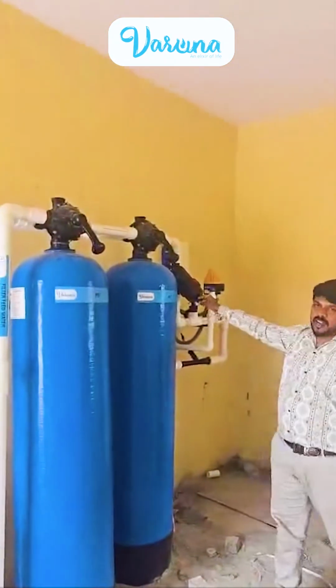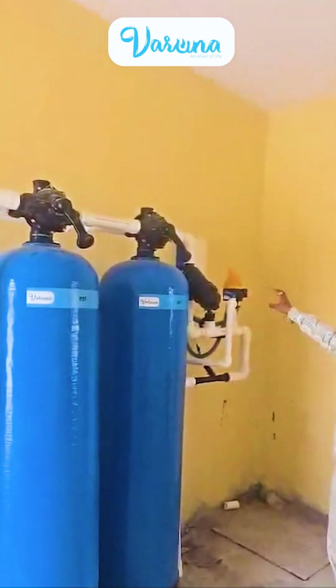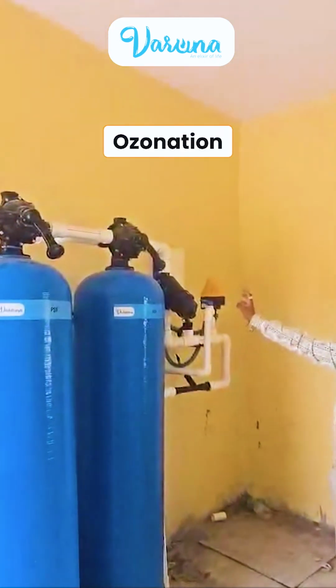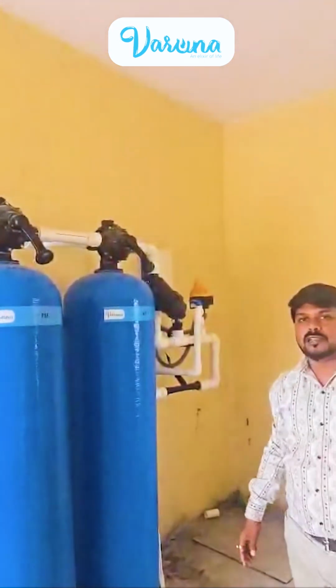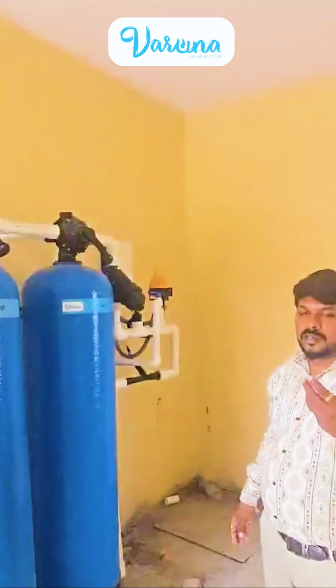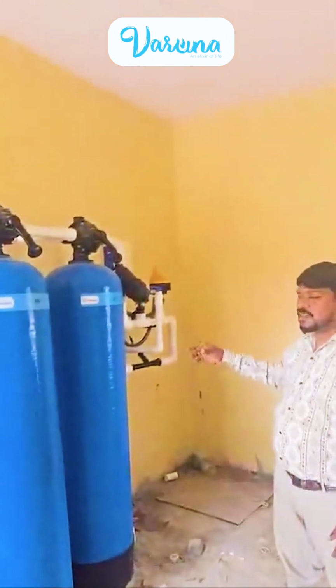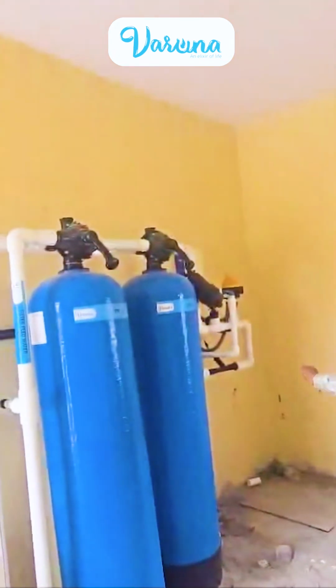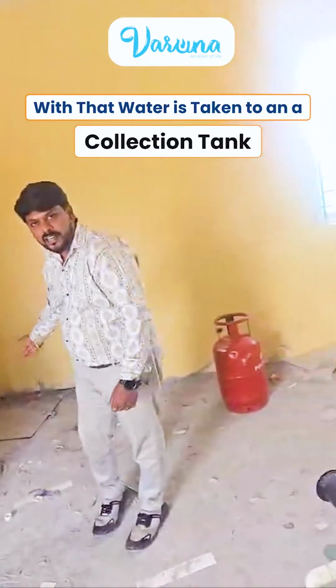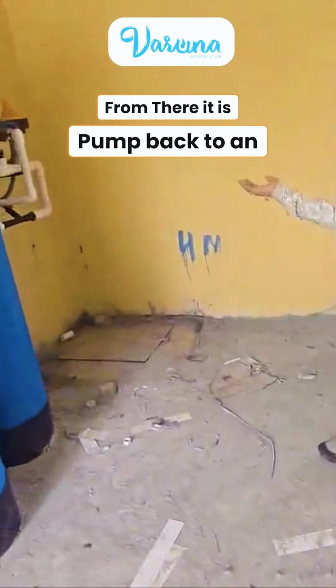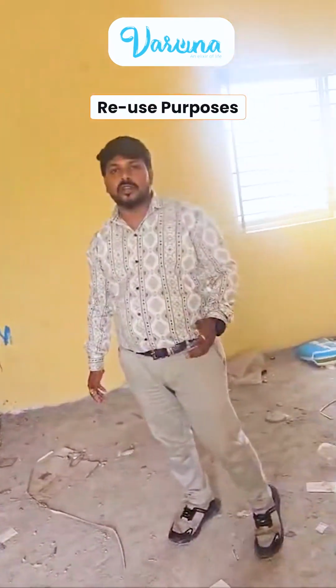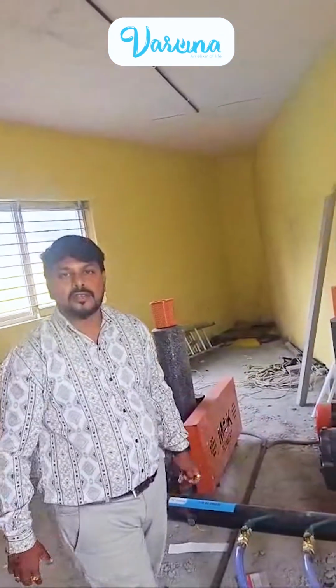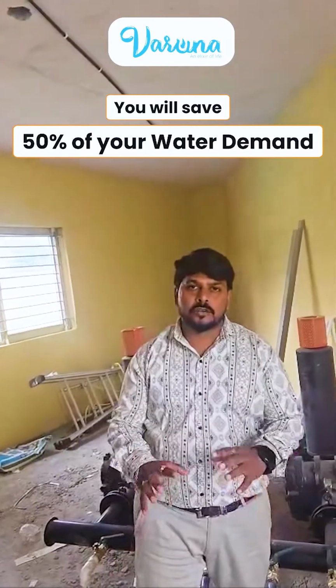In this filtration, after the filters, we have also placed ozonation. With the help of ozonation, whatever microbial contamination is left over is further addressed. With that, water is taken to a collection tank. From there, it is pumped back for reuse in the garden and for flushing, back to the flushes. In this way, if you organize this in your institutions, you will save 50% of your water demand.